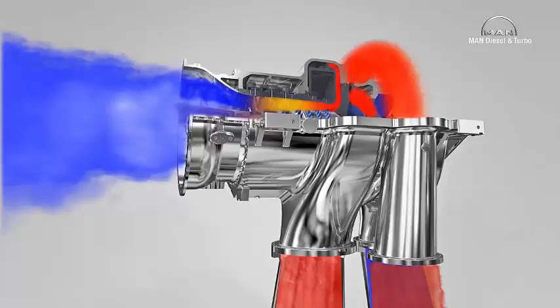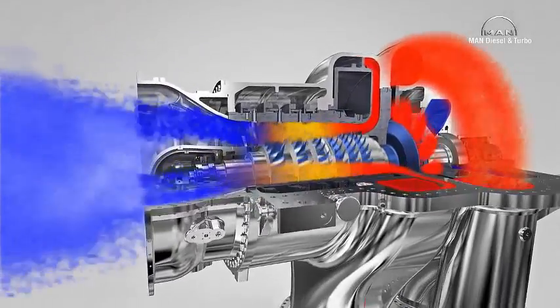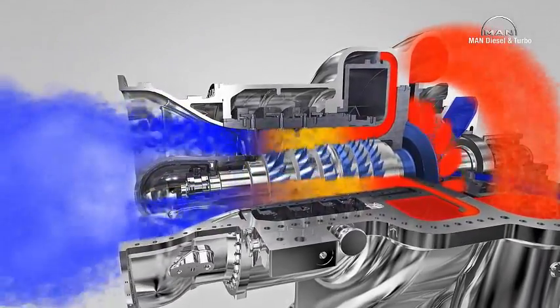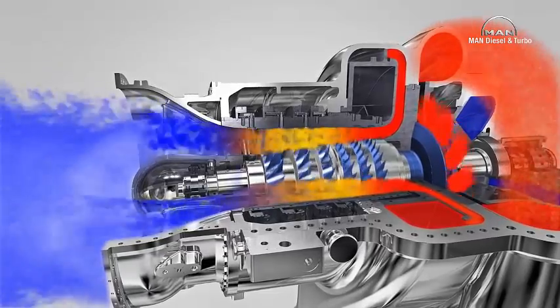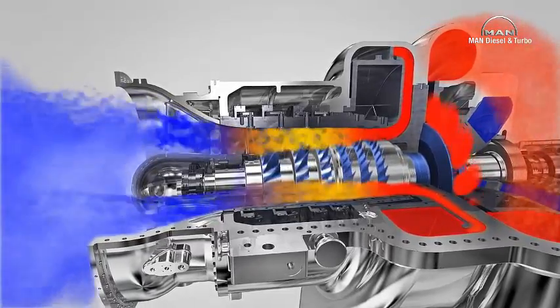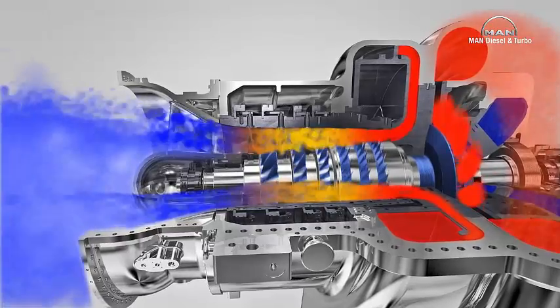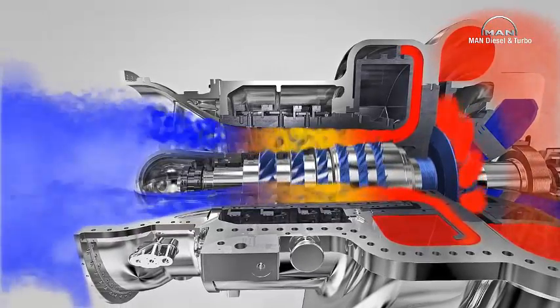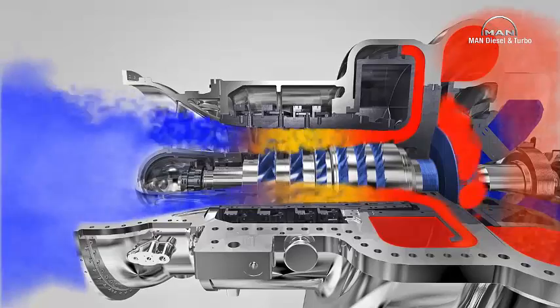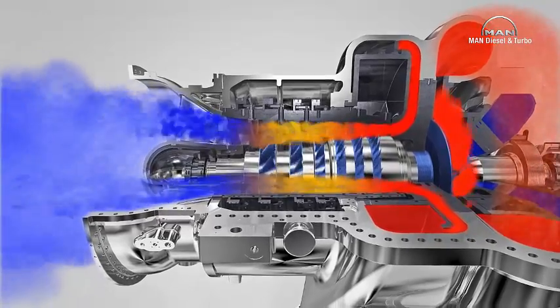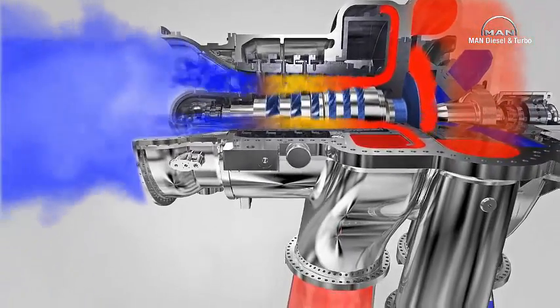Let's now take a look at the axial stage group. As they rotate, the blades strike the gas, guiding it backwards and also compressing it. This process generates a flow along the axis. That's why the machine is called an axial flow compressor. The outlet casing guides the compressed gas to the outlet nozzle.